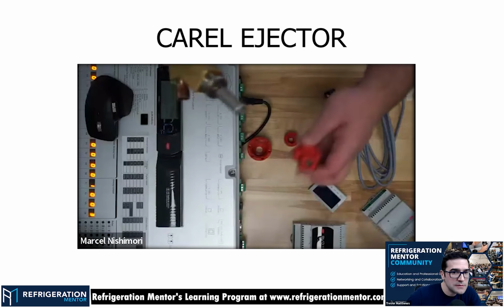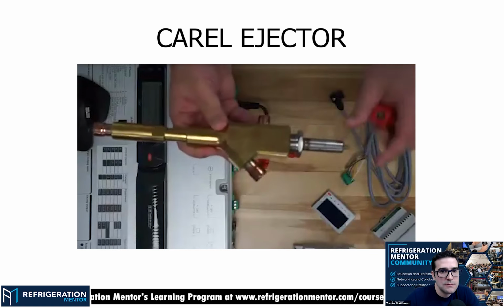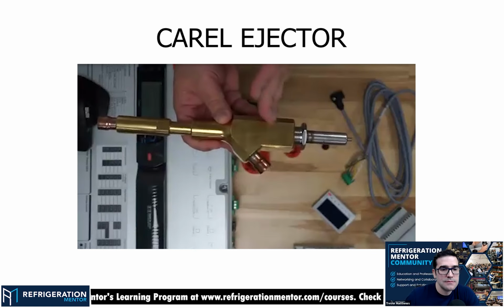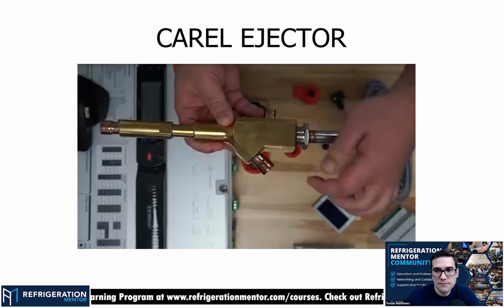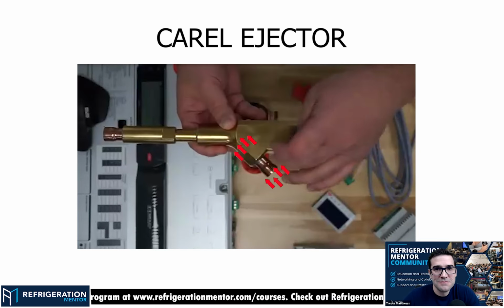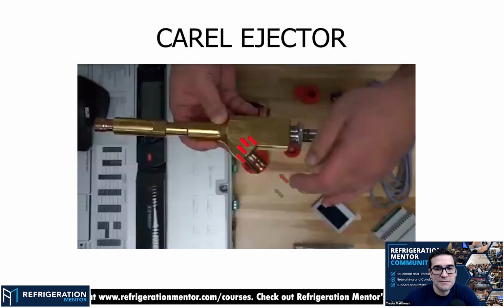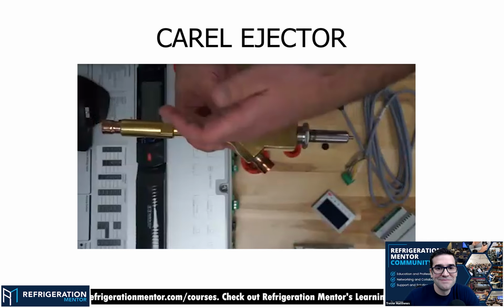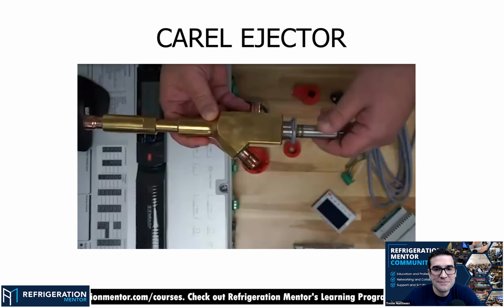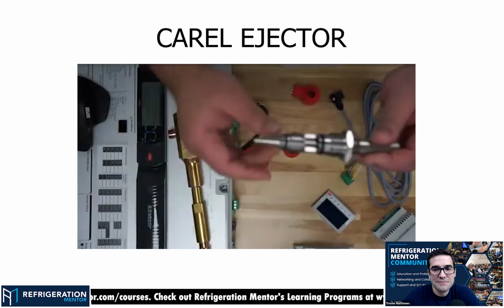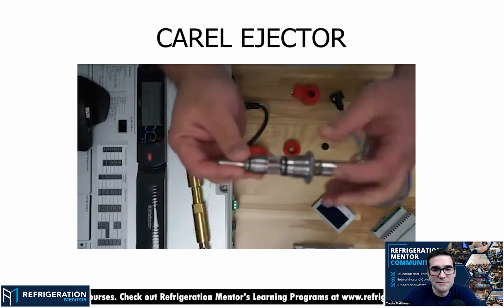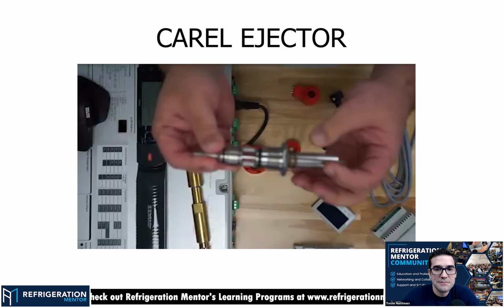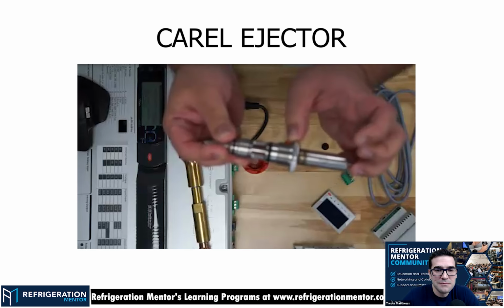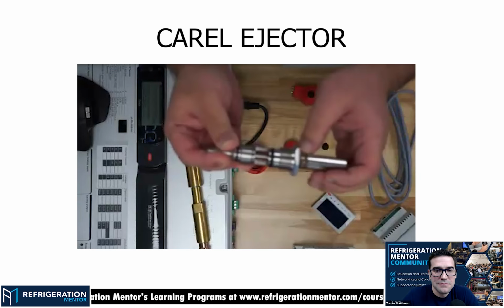So this is the ejector of CAREL, okay? So we have our body. The gas cooler flow comes from this direction, and we have the suction coming from this direction. If you see, also the geometry of the ejector would allow the suction from MT to be more fluid inside the ejector. And here it is what we call our cartridge, and it works with the same principle as a bipolar drive. In fact, this motor is like a bipolar that CAREL manufactures.